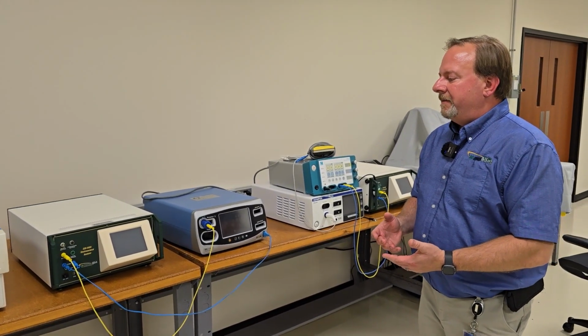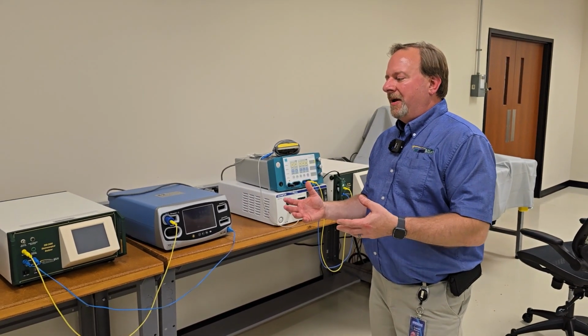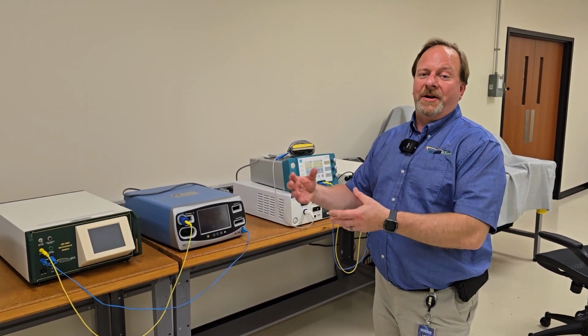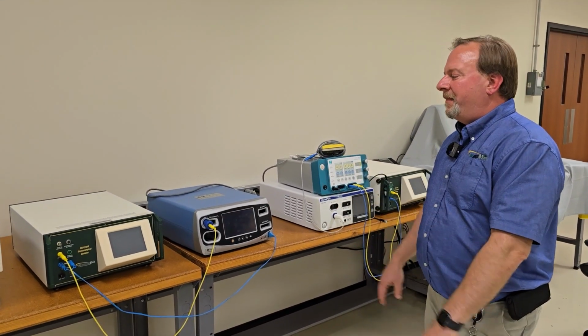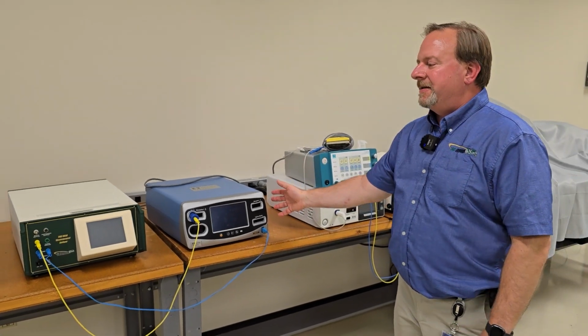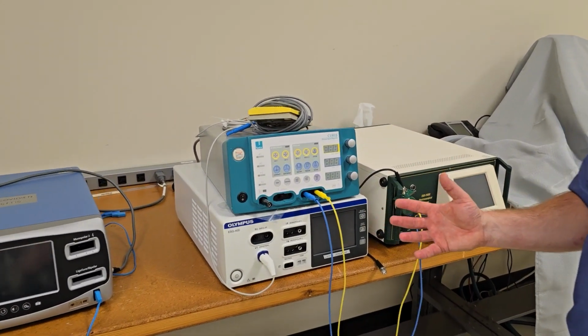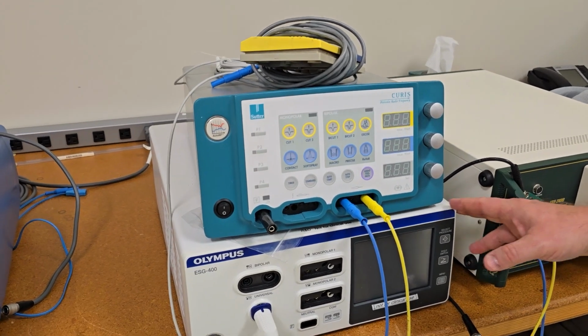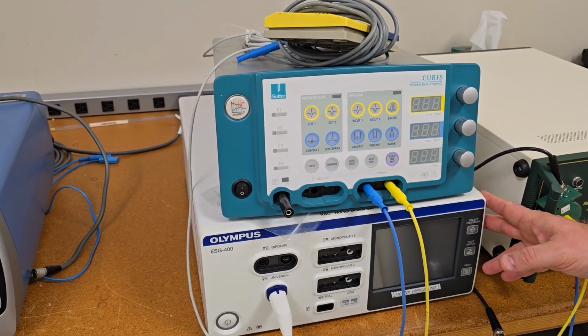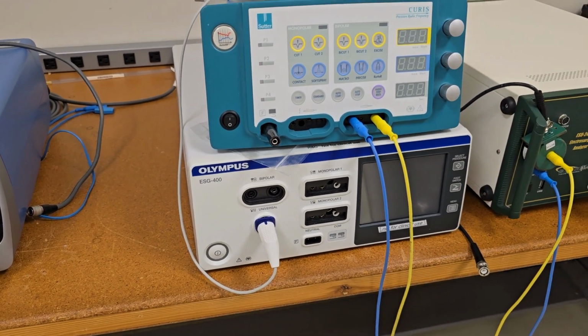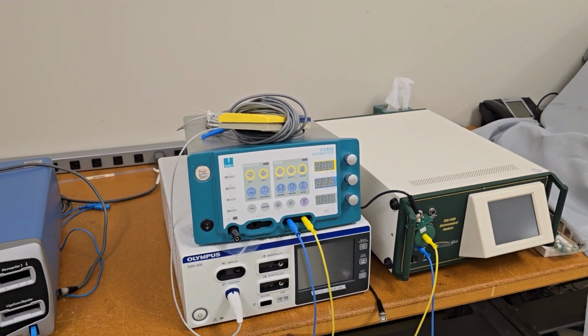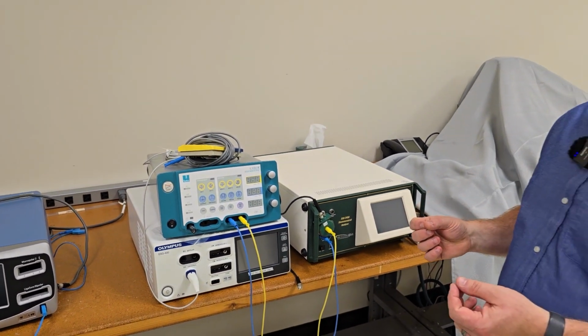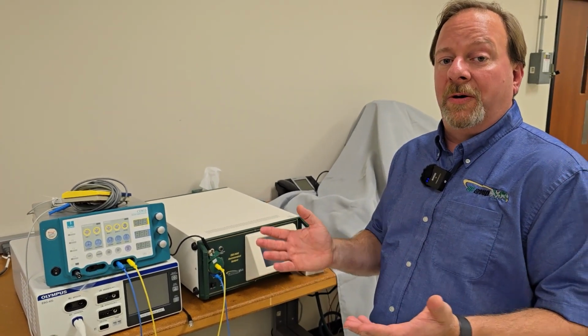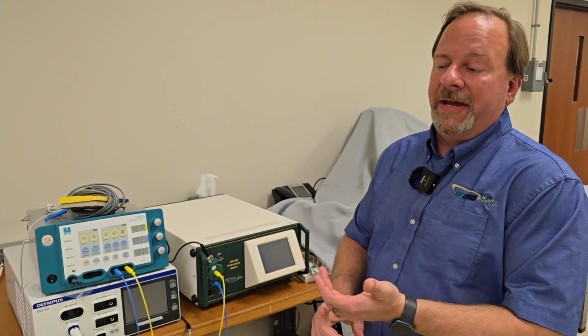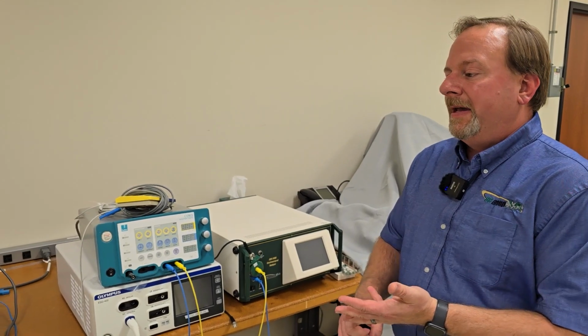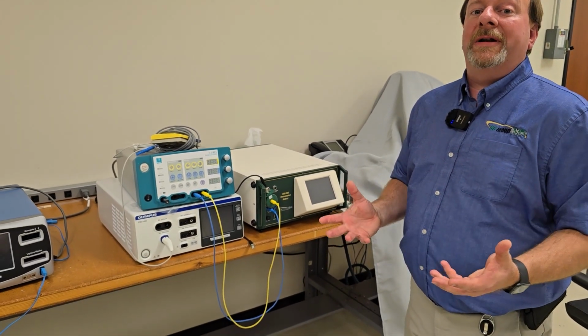And so as we went on, then they wanted integrated loads, right? Then we wanted to automate it, and it's just one step after another. Then they came out with the FT10. Along those lines, some of the new device manufacturers, such as Olympus, came out with these pulsed waveforms unlike anything we'd seen before. Typically, like for the ConMed 5000, the pulsed waveform was either on or off. So the ESU 2050P and the ESU 2400 could read those signals, no problem.